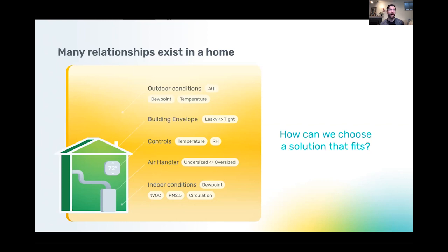So I'm going to say something really shocking here and abhorrent. Almost all IAQ solutions are controlled based on a temperature sensor on your wall. Rick Sims calls this the hope-based control strategy. So how can you dehumidify the air if your air conditioner is off and your dedicated dehu was linked to your central air system? How can your filter run if the central air handler, controlled by heating and cooling calls from the thermostat, is off? You're not going to get filtration. How do you get ventilation if you have passive ventilation through your air handler and that air handler is turned off because the set point is satisfied?